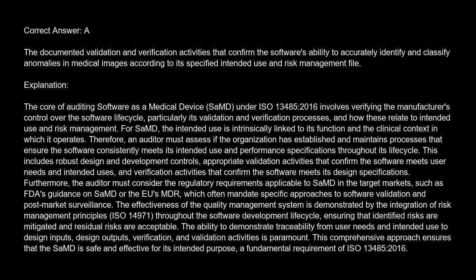Furthermore, the auditor must consider the regulatory requirements applicable to SaMD in the target markets, such as FDA's guidance on SaMD or the EU's MDR, which often mandates specific approaches to software validation and post-market surveillance. The effectiveness of the quality management system is demonstrated by the integration of risk management principles, ISO 14971, throughout the software development lifecycle, ensuring that identified risks are mitigated and residual risks are acceptable.